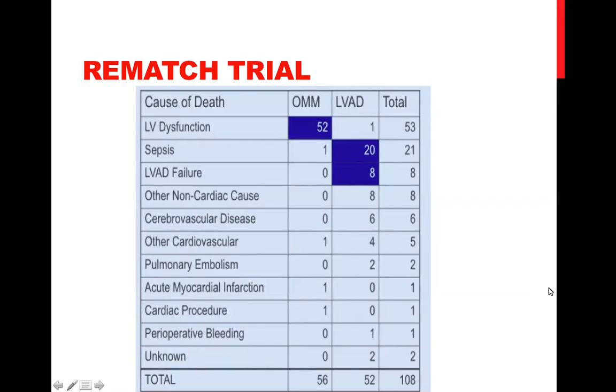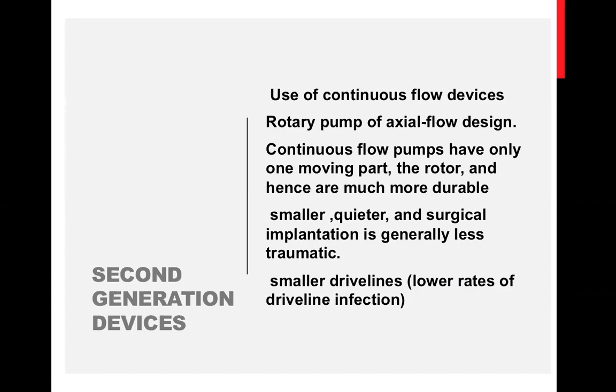Second generation tried to solve the problems with the first generation by introducing continuous flow devices, rotary pump of axial flow design, and continuous flow pumps have only one moving part, the rotor, and hence are much more durable and smaller, quieter, and surgical implantation is generally less traumatic, and they have smaller drive lines and a lower rate of drive line infection.